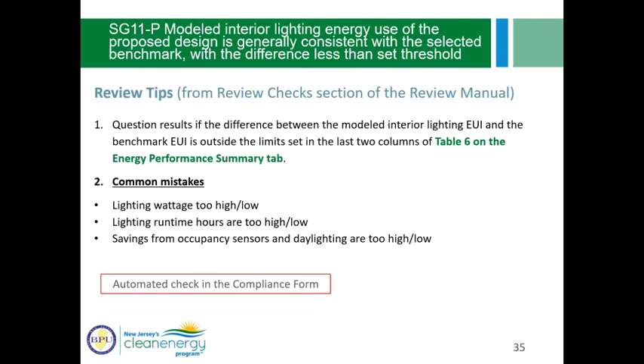When you see, for example, that the proposed lighting EUI is significantly different from the proposed EUI for the benchmark, it might be that the modeled wattage is too low or too high, or runtime hours are too low or too high. Maybe there was a mistake in modeling the occupancy sensors, and the savings are showing as too high. These common mistakes are in the review manual to help you with troubleshooting the issue.